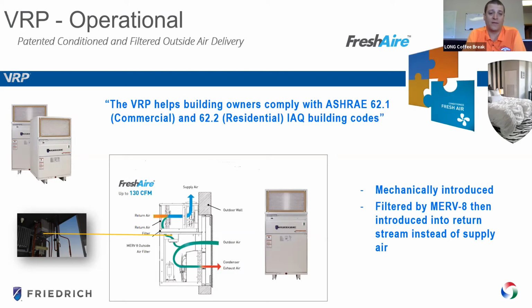But with this unit, they have the ability to provide up to 130 CFM of fresh outside air through 2 fans that you can see comes through the outside air, goes through a filter to make sure you're not introducing particles into the space, mixes with the return air, and then is conditioned at the coil. So a lot of VTACs and PTACs will just have a passive opening. So essentially what the supply fan is able to pull out is what you're going to get for your outside air. With the VRP units, you actually have dedicated fans that will turn on and guarantee that you're bringing that air into the space.